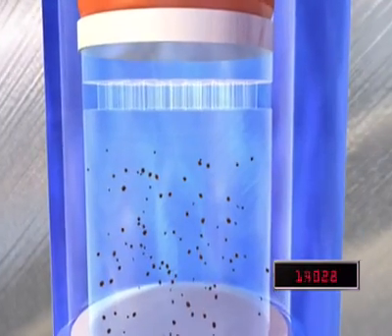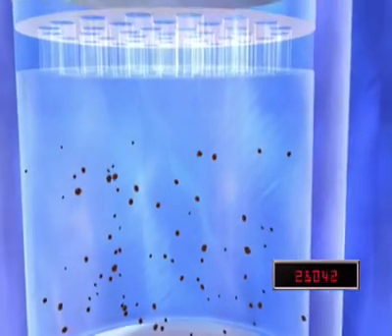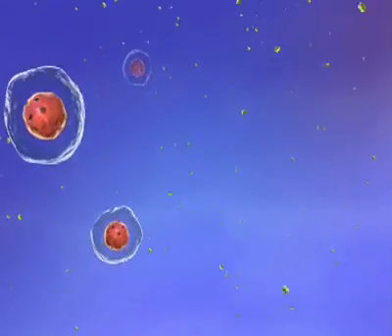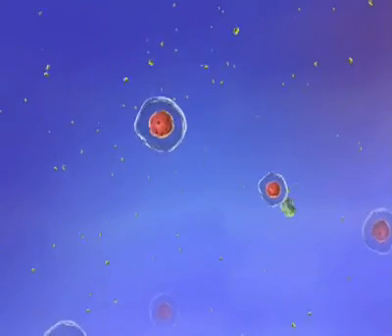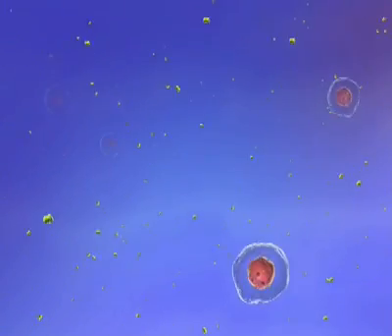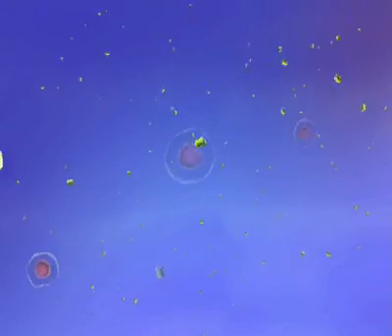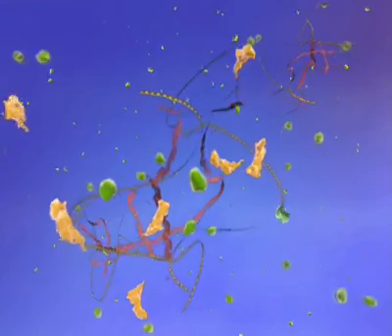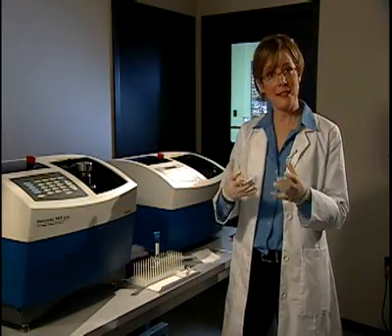The tick rapidly mixes with the added processing buffers. When pressure is released, the partially lysed tick is pulled back through the lysis disc and into the sample chamber. With each subsequent pressure cycle, this process is repeated. The combination of physical passage through the lysis disc, rapid pressure changes, and other biophysical mechanisms exerted during the PCT process breaks up the cells and tissues of the tick, as well as other organisms in the sample, such as the bacterium that causes Lyme disease.